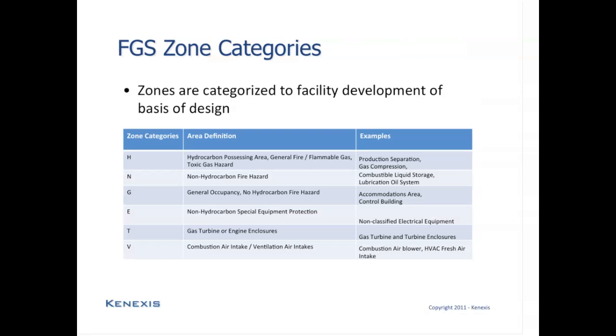Now, once all of the zones have been defined geographically, you're going to want to categorize them, and the categorization of those zones is then going to help you to select the mitigation techniques that are going to be employed for that specific zone. The categories of the zone that are typically used in performance-based fire and gas design are shown in the table below. The zone categories are H, N, G, E, T, V, which all define different attributes of a process zone.